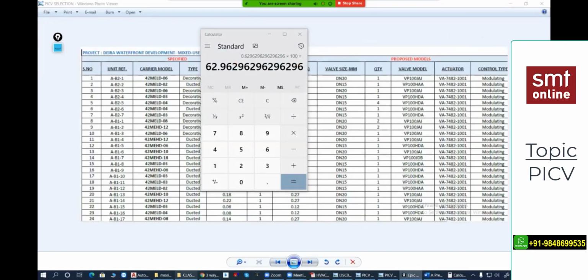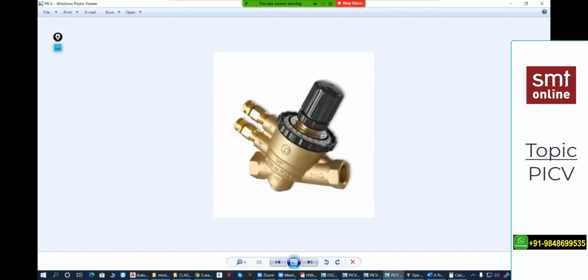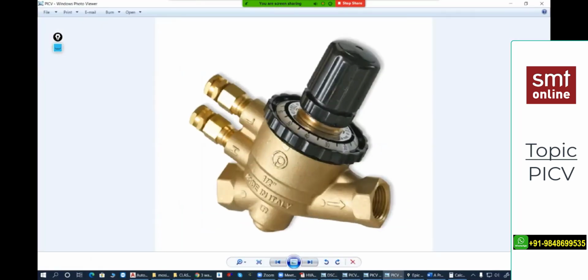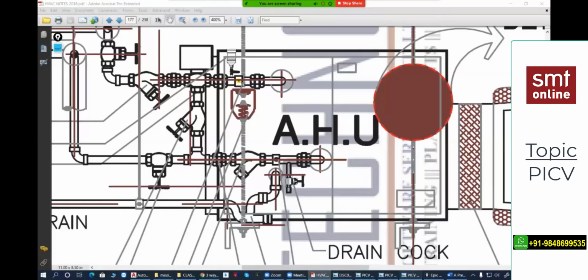I'll show you one image. In this image, can you see this percentage rating? Even in the video, that percentage rating. So we need to set this to say 62%. Not exactly; the manufacturer will give it to you as per the software calculation. You may get slightly more or slightly less, say 60 or 65, close to that. So after installation only, you need to set the percentage. That's it. No balancing is required. Nothing is required. Getting my point? Okay, sir. So this is very simple compared with the two-way and three-way modulating valve.